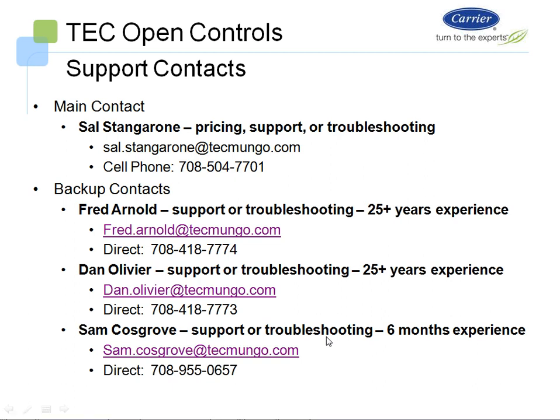Tim's question: does carrier require an interface card to talk to another manufacturer's equipment? The only way it would require an interface card is if it does not speak BACnet, BACnet MSTP, or IP. Otherwise, they can standard speak with any other controller that speaks those languages, so you shouldn't need anything special.